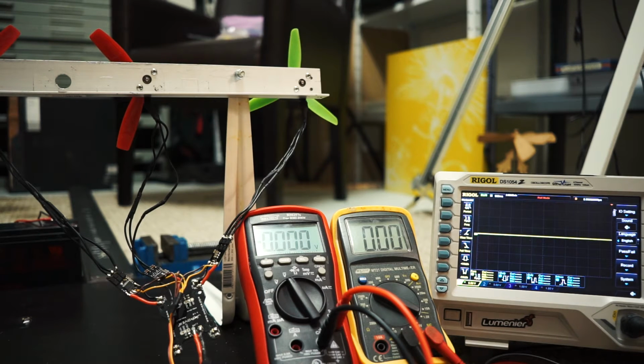It is a known gauge of wire, 18 gauge in this case, a known length of wire, and therefore I know the voltage drop across it - it's calibrated with the exact length to give me 1 millivolt per amp.